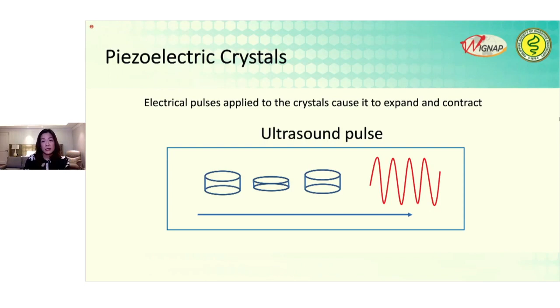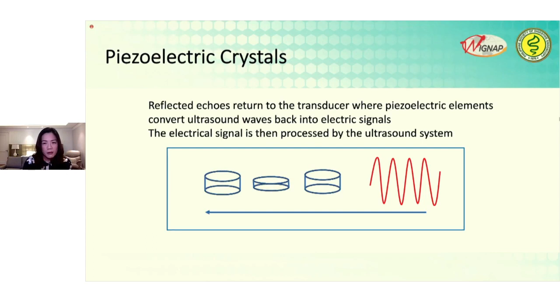So the sound wave, after it hits tissue, will be reflected back to the transducer, and the piezoelectric crystals then convert the ultrasound waves back to electrical signals that are then fed into the machine to produce an image. Note that in producing an image, the pumping in and out, or the expanding and contracting, of the crystals to produce ultrasound waves occurs maybe 1% of the time, because the rest of the time is spent waiting for the reflected sound waves or the echoes.